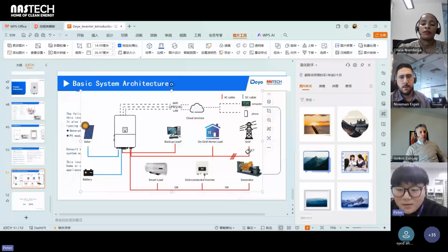So maybe you need more, like five modules together, then you can achieve the start voltage of the inverter. And for low voltage, it actually depends on your production and the load consumption, how much power you want to store. Then you can decide how many modules you want to parallel together. And for high voltage, besides the start voltage, you also need to consider your load consumption and production to decide your energy capacity.